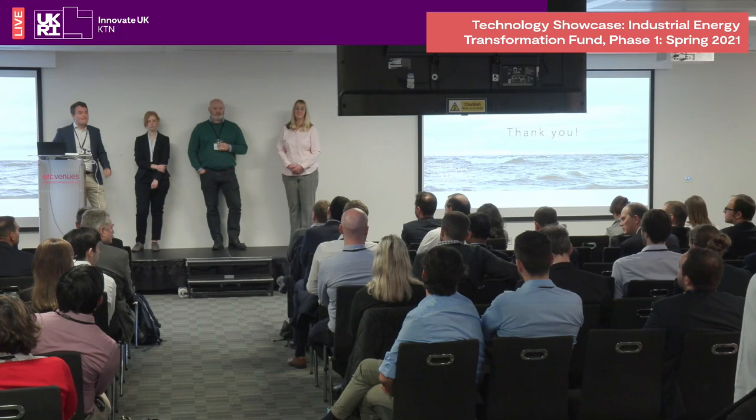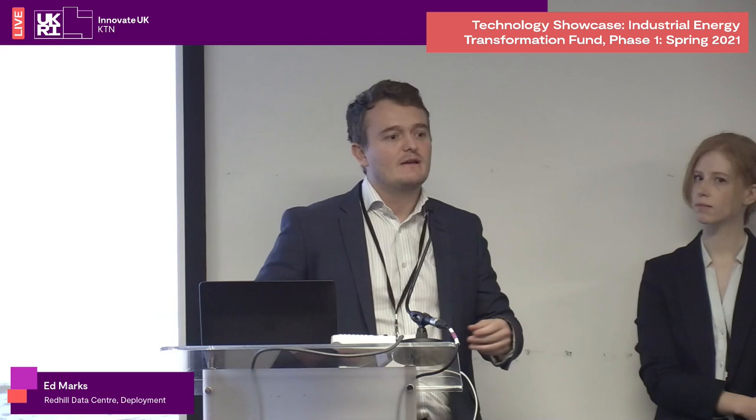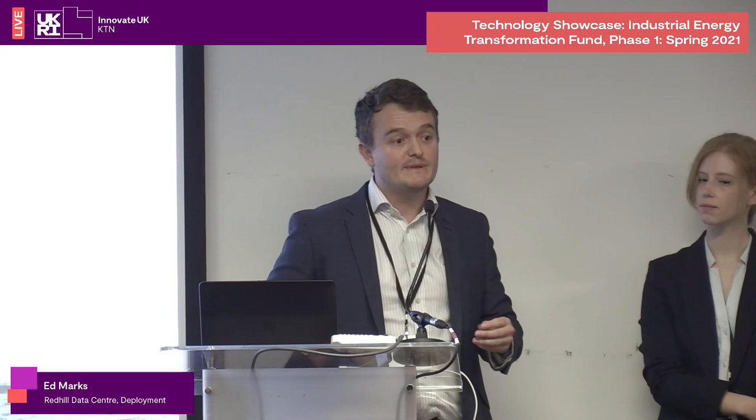Yeah, so it's a tricky one because obviously leveraging evaporative cooling helps energy, but the other issue that we have is the amount of water stress, particularly in the locations where most UK data centres are, which is in the ring around London. So almost water usage becomes just as scrutinised as energy usage at the moment, not just here but globally. So generally, we've seen some companies operate with an approach of just not touching evaporative cooling, just using air cooling.